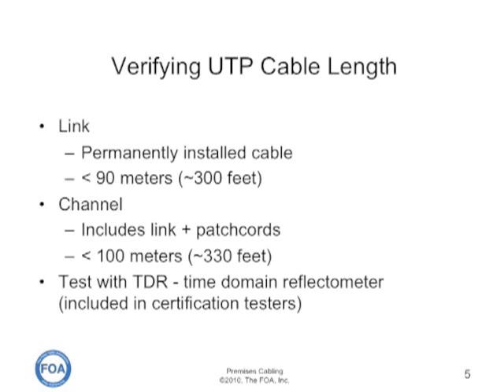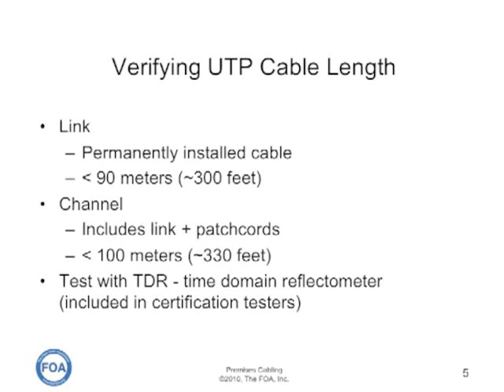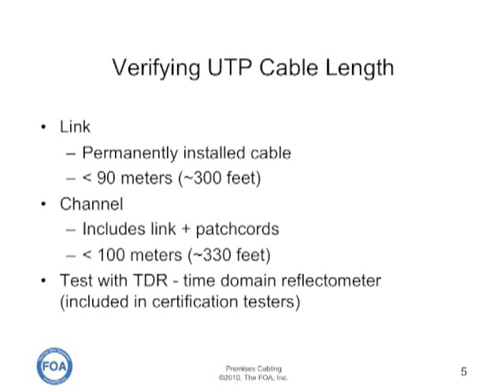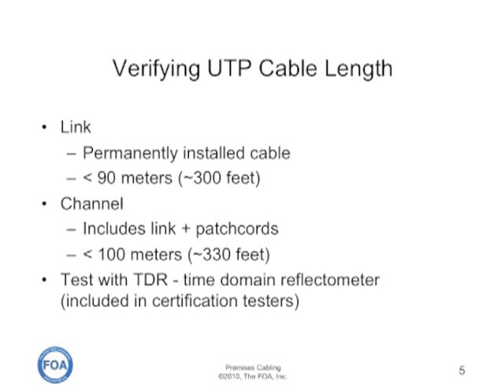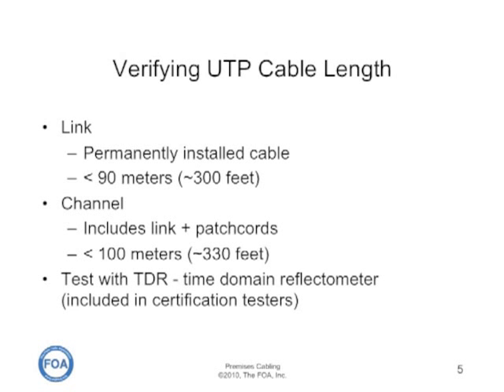The next test is to verify the UTP cable length. In a link, or the permanently installed cable, it must be less than 90 meters or about 300 feet. The channel, which includes the link plus patch cords, must be less than 100 meters. You can test this with a TDR, or time domain reflectometer, which is a tool included in all certification testers as well as being available as a standalone tester.